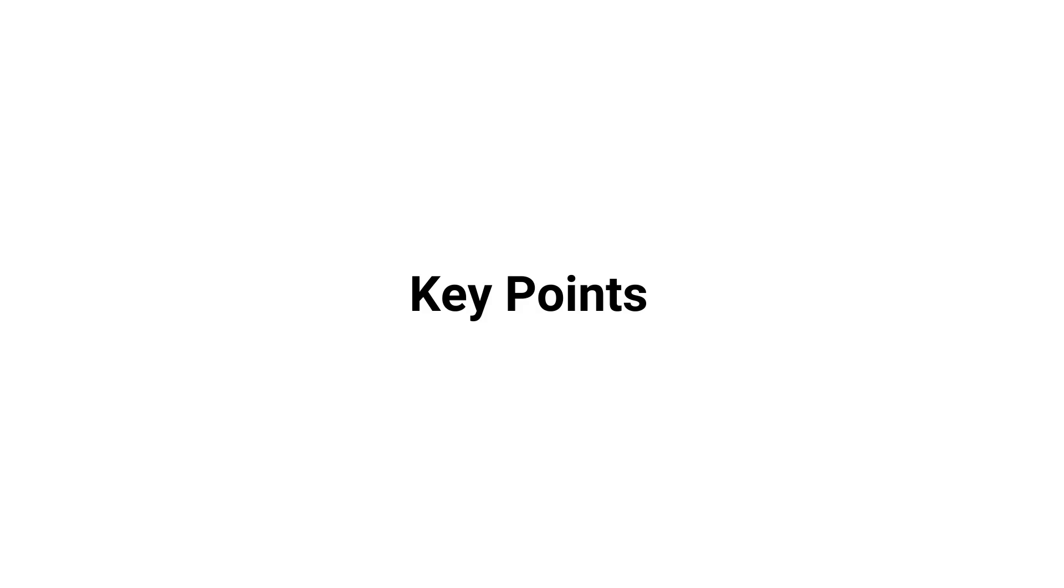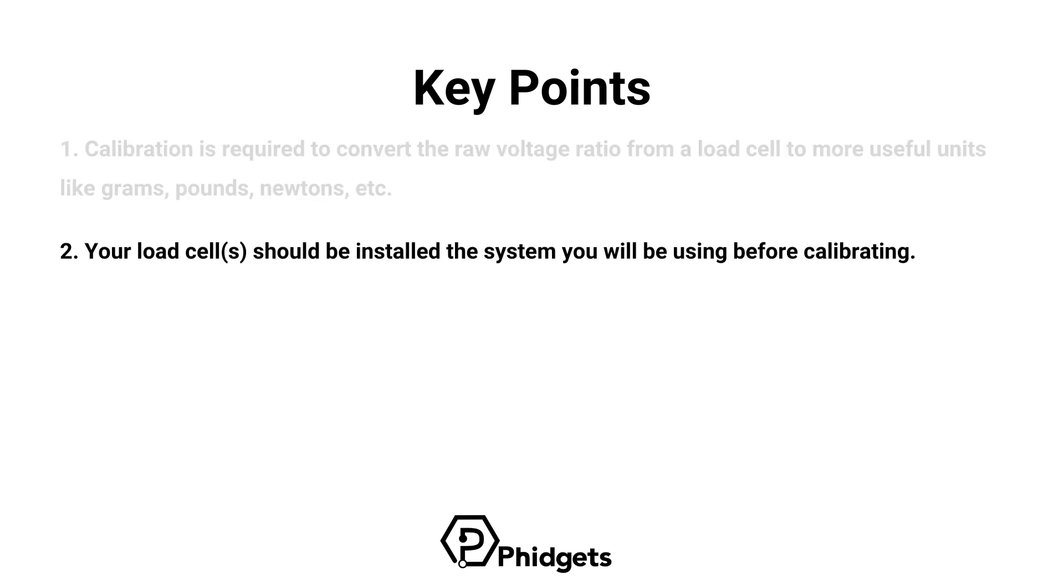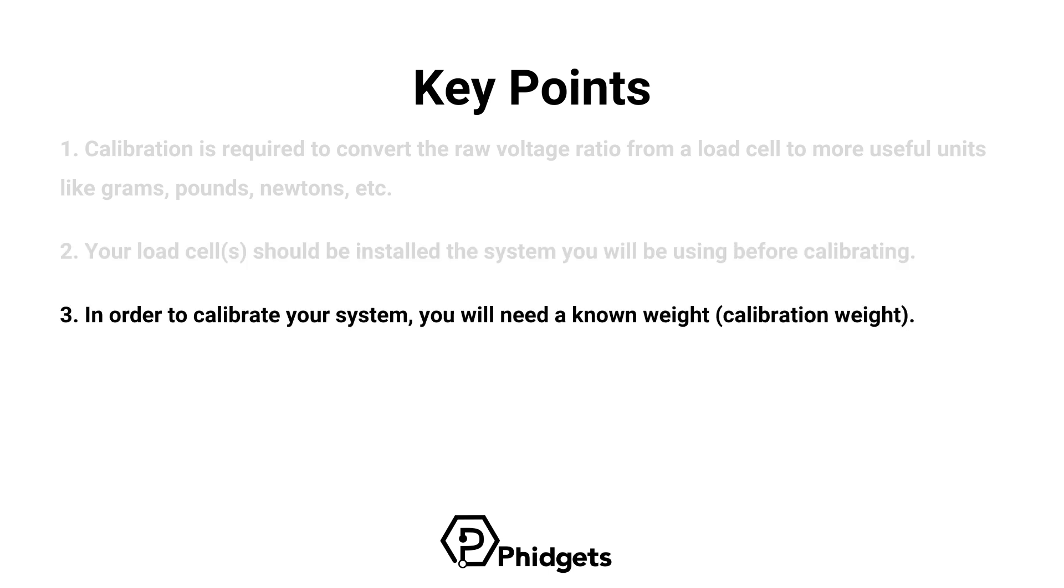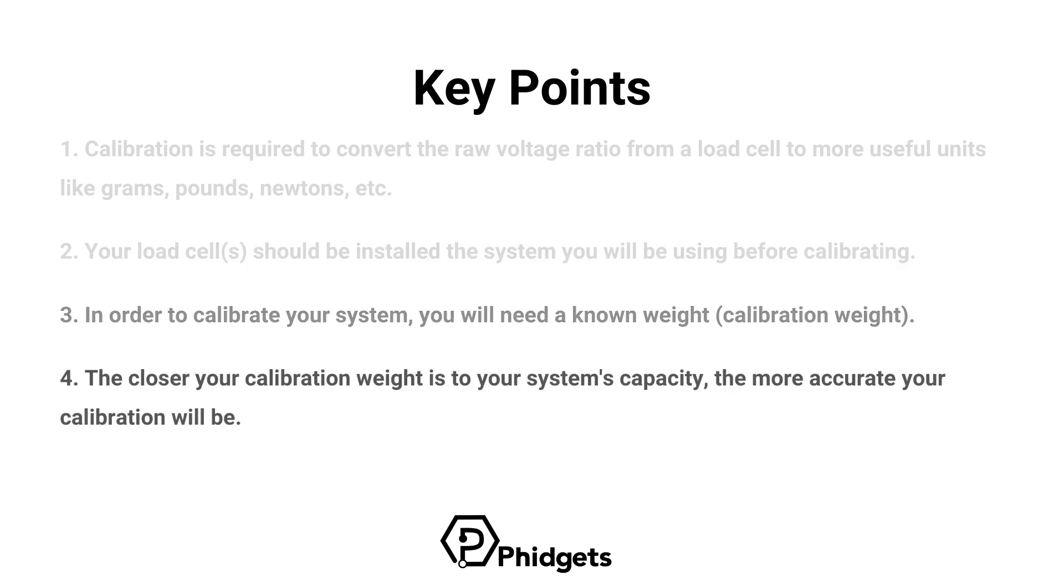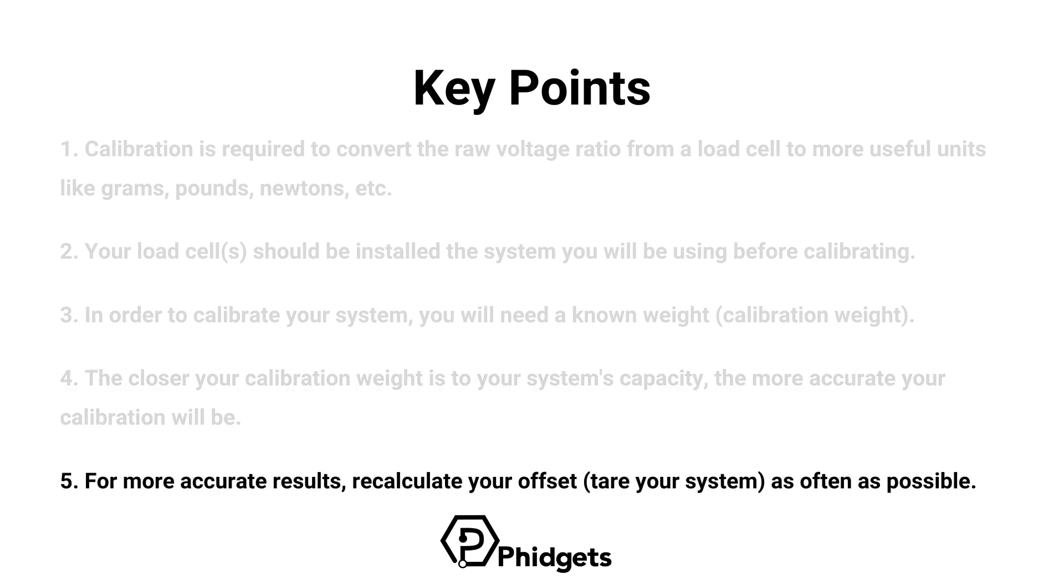Here are some key points to summarize what we've learned. Calibration is required to convert the raw voltage ratio from a load cell to more useful units like grams, pounds, newtons, and more. Your load cell should be installed in the system you'll be using before calibrating. In order to calibrate your system, you'll need a known weight. The closer your calibration weight is to your system's capacity, the more accurate your calibration will be. For more accurate results, recalculate your offset as often as possible.